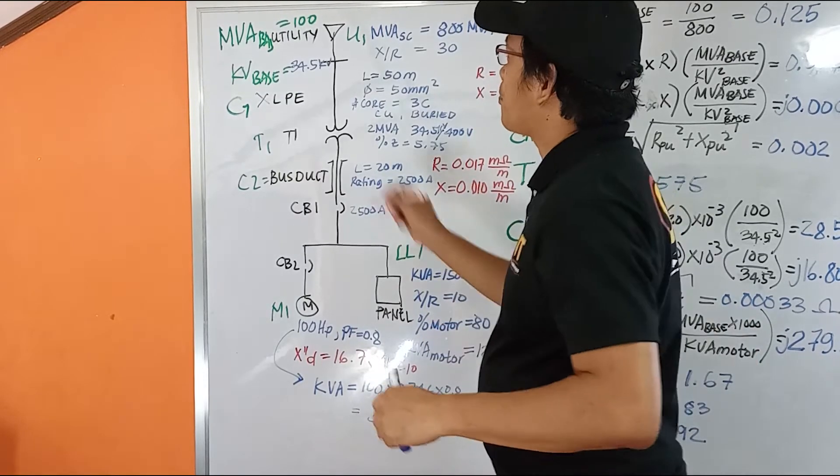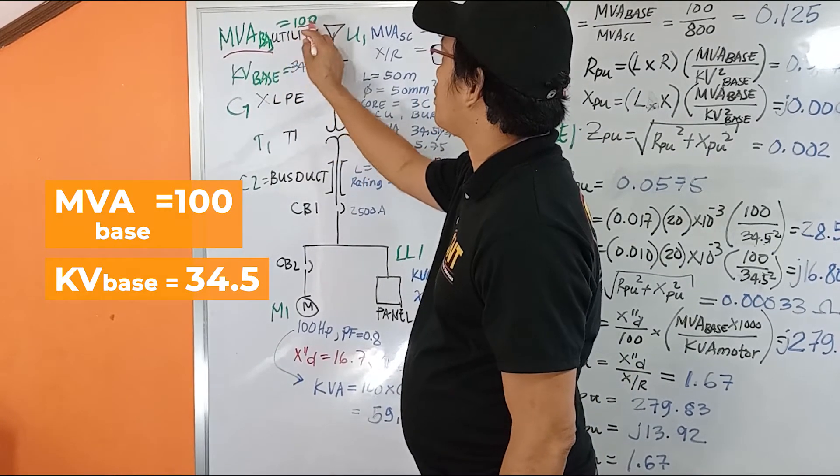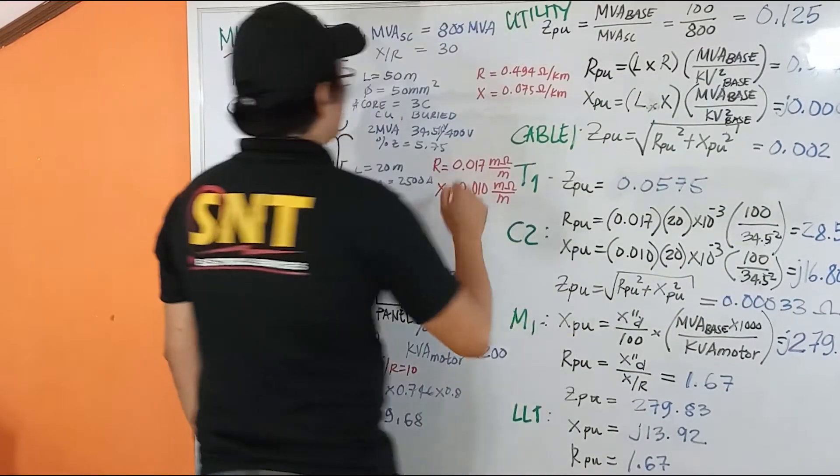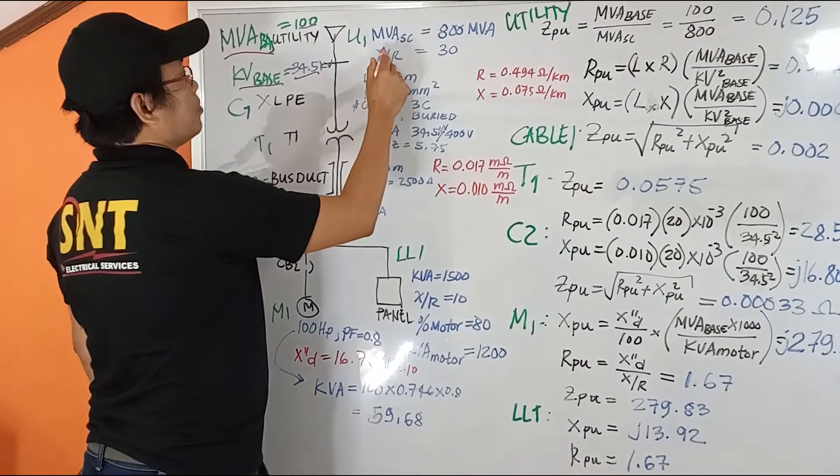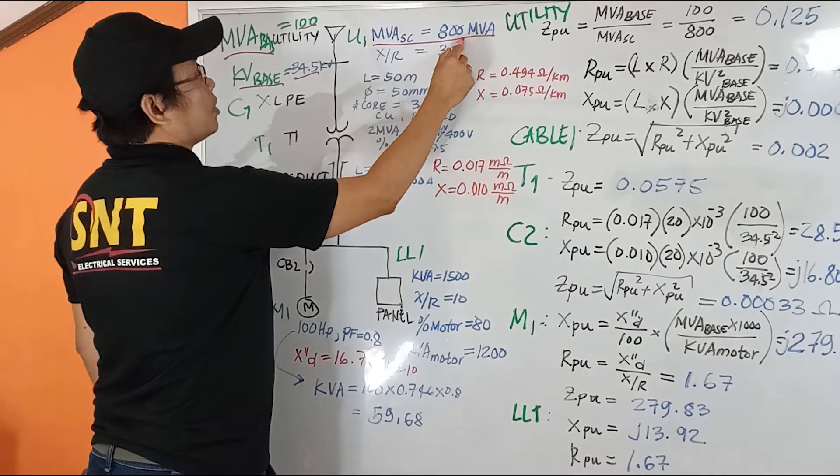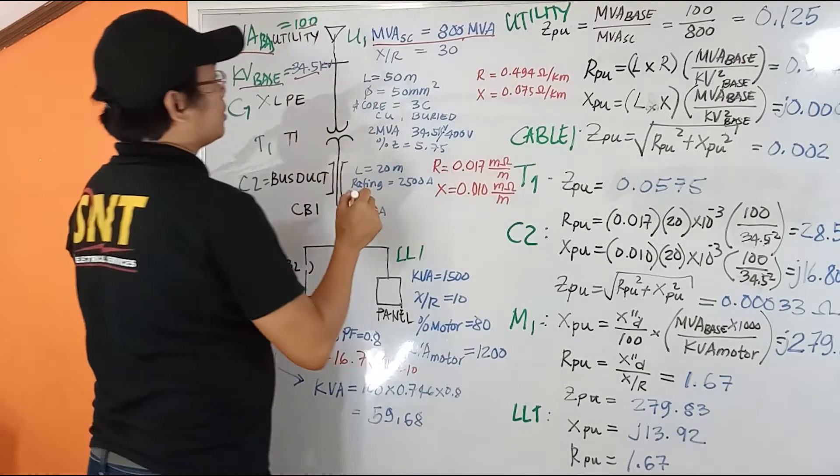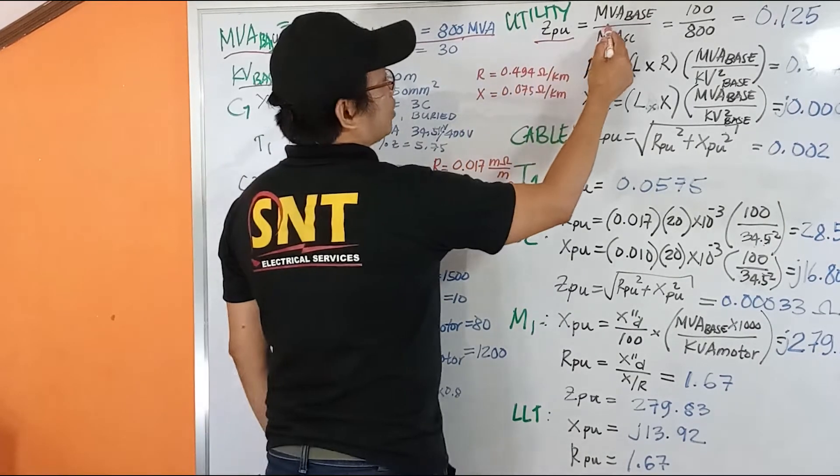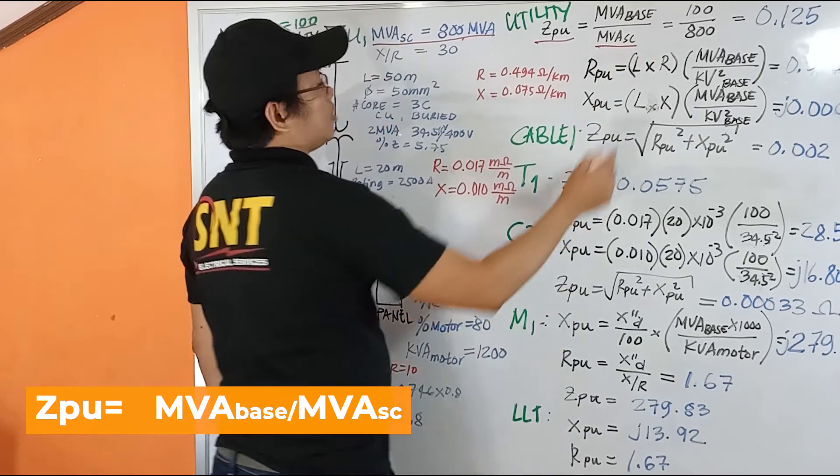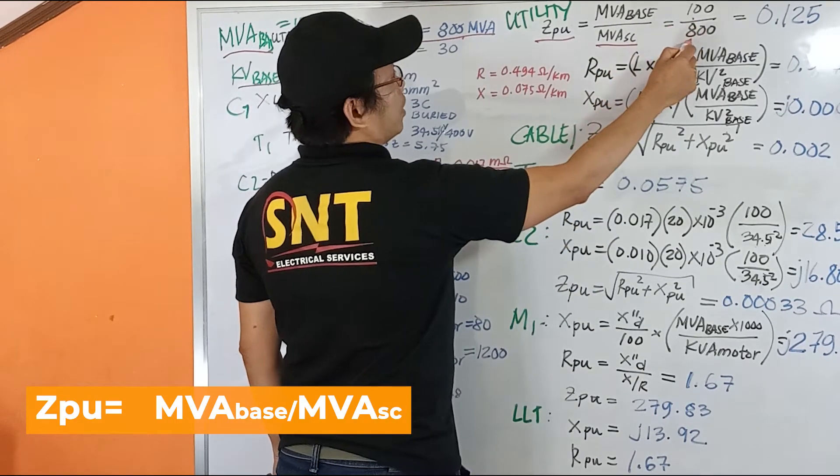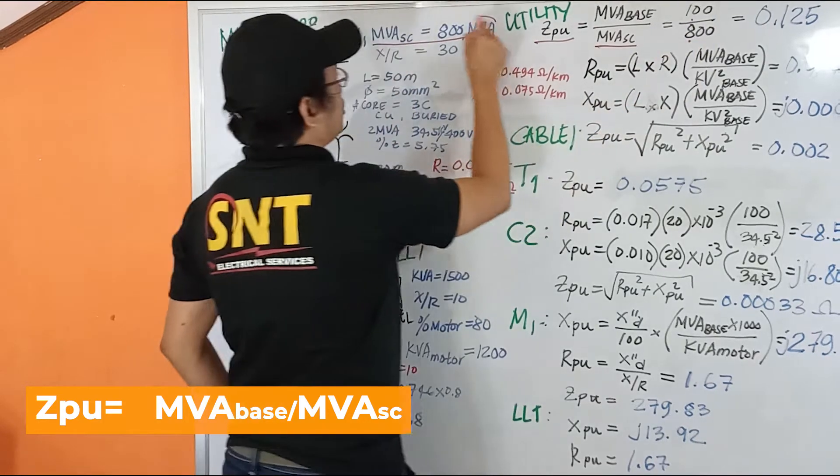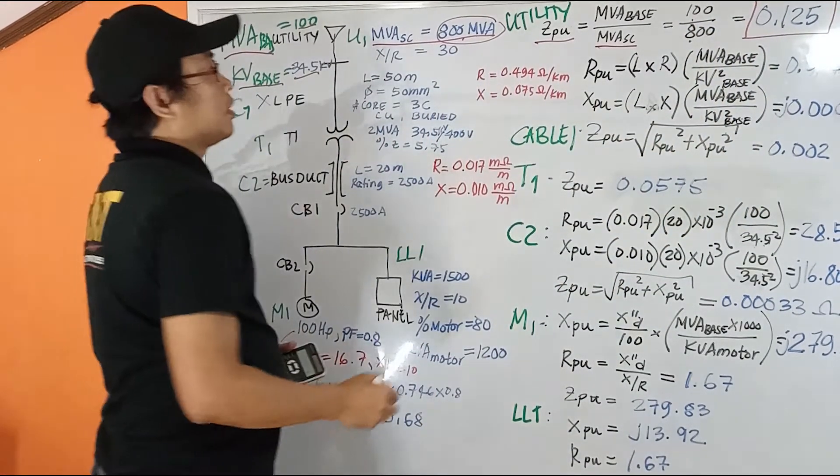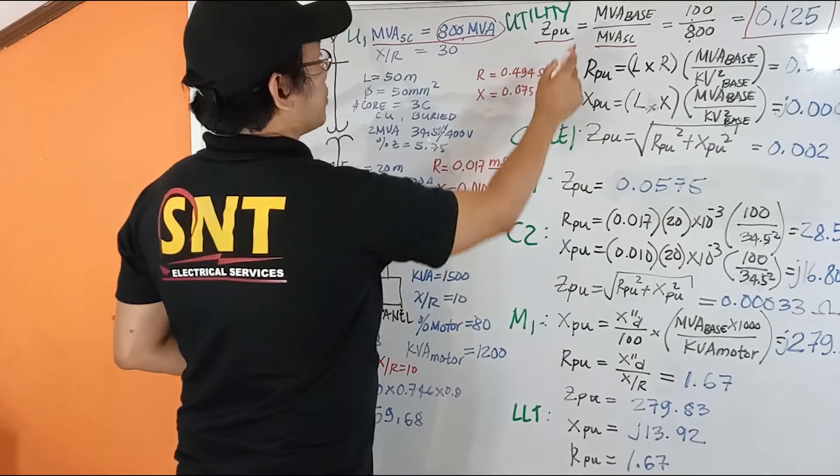So let us use the MVA base of 100 and the kV base of 34.5 kV. The given MVA short circuit of the utility is 800 MVA, and we calculate the per unit impedance using MVA base over the MVA short circuit. Given our MVA base at 100 and 800 as our MVA short circuit, we get this value: 100 over 800. That's for our utility.